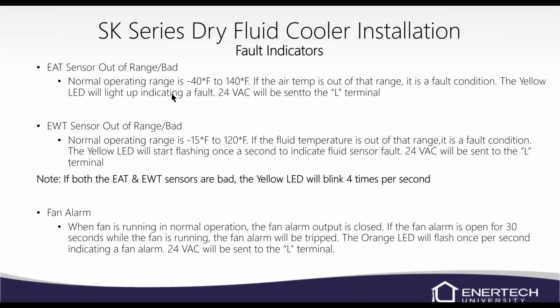EWT is an entering water temperature sensor. Its normal operating range is -15 to 120. Obviously, if it gets out of that range, it's a fault condition, and it's, again, the yellow LED will start flashing. If both the EAT and EWT sensors are bad, the yellow LED will blink 4 times. Now, you don't have to remember how many blinks are going to mean this or that. It will tell you in the manual and on the wiring schematic on the door of the unit.